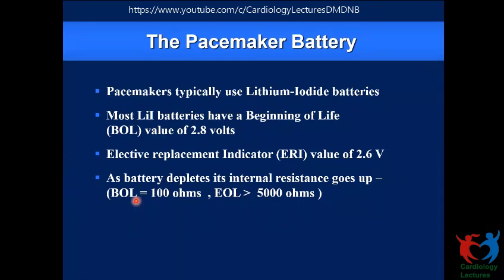A lithium iodine battery typically has a compartment of lithium and an iodine, separated by a semi-permeable membrane. Initially, it has a very low impedance, of the order of 100 to 200 ohms. When you connect it, the current flows through that. Inside the battery, it forms a compound, lithium iodide. It builds up over a period of time and gradually increases the impedance of the battery. That's why the battery voltage comes down over a period of time. At the time of ERI, it will usually be about 3,000 to 4,000 ohms. When it reaches EOL, it is typically about 5,000 ohms.